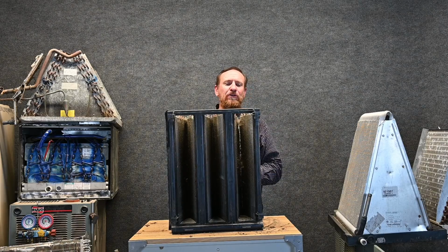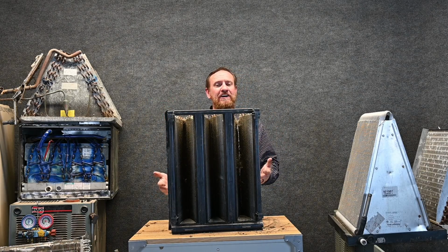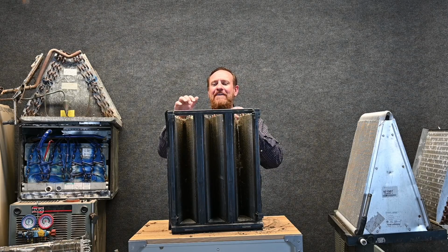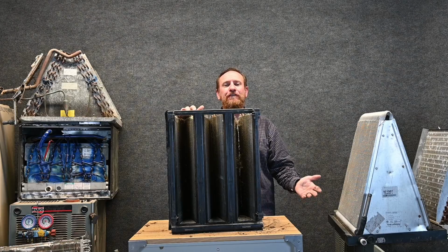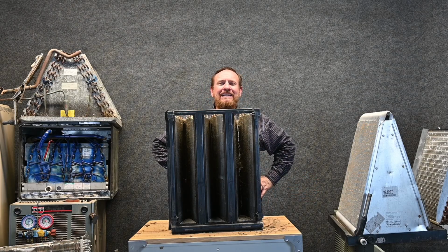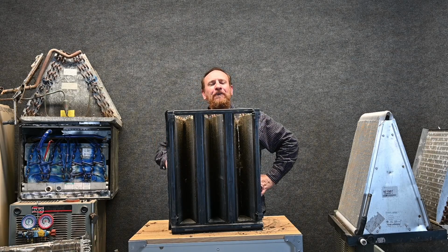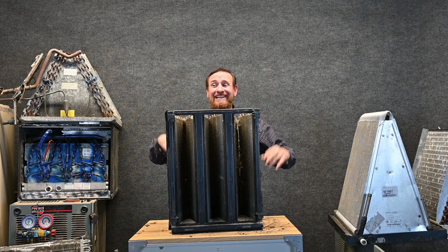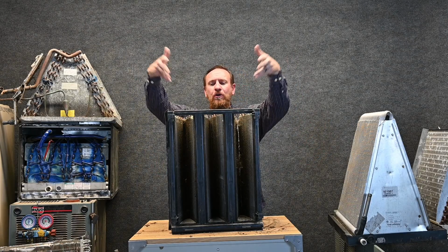On these coil cleanings, if we have good proper filtration and that filter is changed often, we never need a coil clean. I've had customers before where I recommend what filter to use and leave a filter there for them to use, and they've come back and said, "Hey Ty, I didn't like using those filters you left me because they get dirty too fast. I went back to my old filters because they don't get dirty." The dirt's still there. Either it's going to be caught in the filter or it's going to be caught in the evaporator coil.